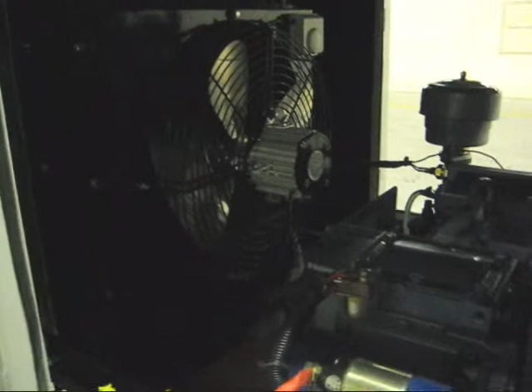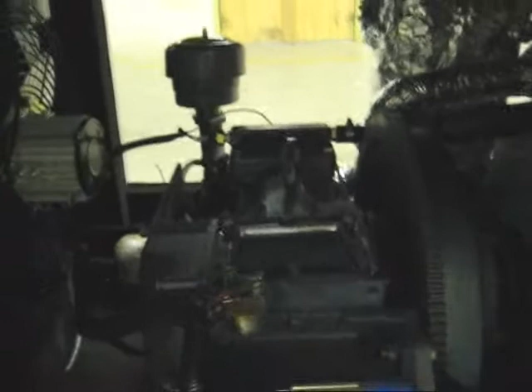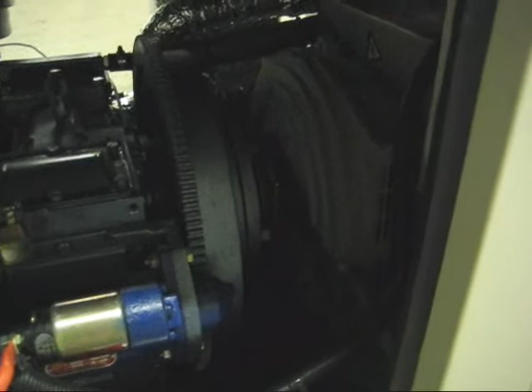What we've tried to do with this is over-engineer everything as much as we can. The engine is designed to be 16 horsepower, running at 2200 RPM. We've down-rated it to 1500 RPM and directly coupled it to the alternator. It's a single cylinder horizontal diesel. It's quite big for the power output, but that's what you need if you want something to last.